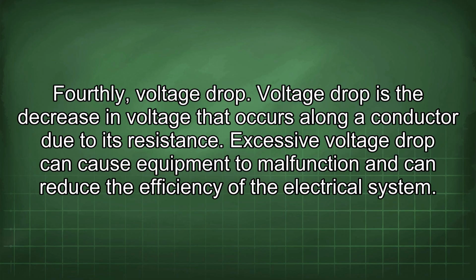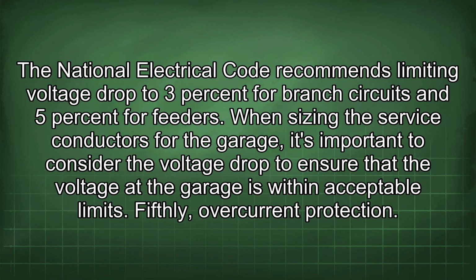Fourthly, voltage drop. Voltage drop is the decrease in voltage that occurs along a conductor due to its resistance. Excessive voltage drop can cause equipment to malfunction and can reduce the efficiency of the electrical system. The National Electrical Code recommends limiting voltage drop to 3% for branch circuits and 5% for feeders. When sizing the service conductors for the garage, it's important to consider the voltage drop to ensure that the voltage at the garage is within acceptable limits.